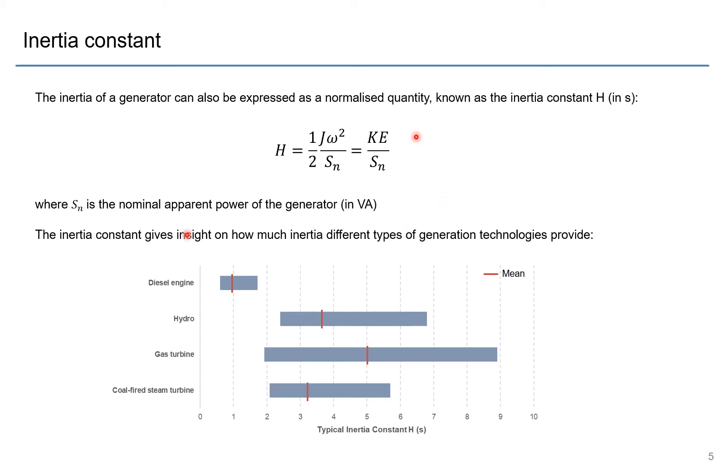So here we have a plot of typical inertia constants for different generating technologies, and we spoke before that diesel engines and combustion engines have quite low inertia. You can see here the range of inertia values is between 0.8 and 1.8, and on the other hand you might have gas turbines and steam turbines have quite high inertia constants.